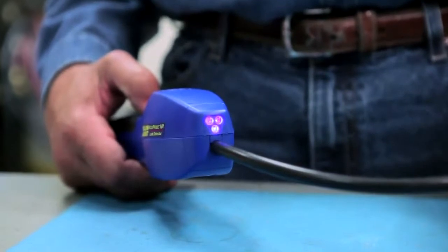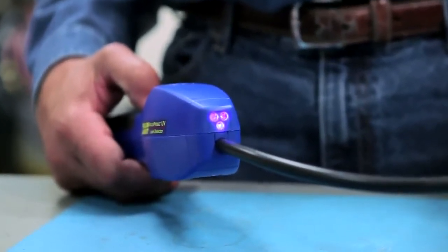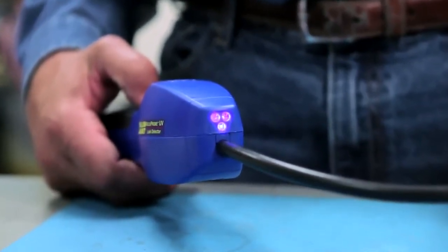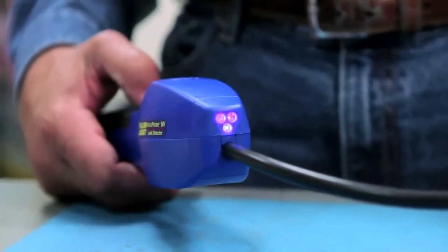The AccuProbe UV also features a three LED UV light system, which works with 395 to 415 nanometer wavelength leak tracing dyes for use on systems that were either installed with or have had dye injected in past service calls.